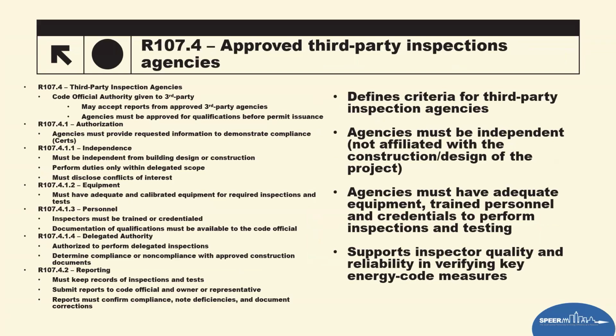One thing they did add, which I was glad to see, they finally addressed, kind of given an outline of using third parties. So that section R107.4 tightens up on how third-party agencies are defined and used for inspections and testing. If your project's using third-party agencies, for example, they're going to verify insulation installation, air barrier integrity, duct leakage testing, envelope testing.